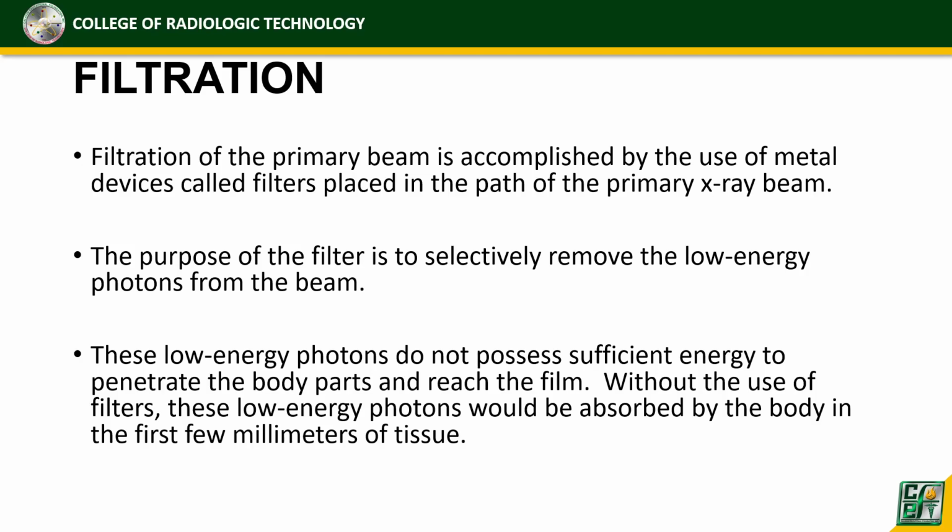The secondary function or purpose is to filter out low energy photons from the beam. That means it removes low energy photons that have no ability to penetrate body parts and reach the IR.